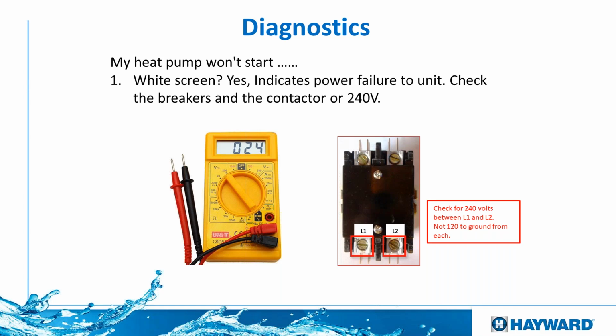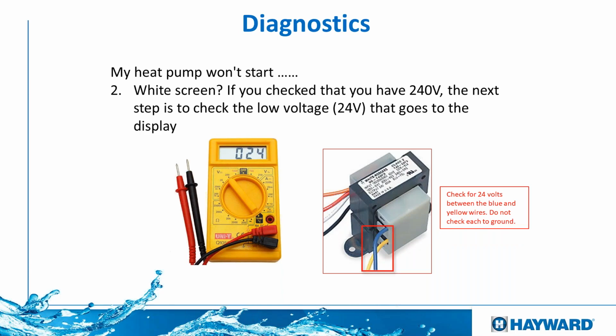So again, if the heat pump won't start, the screen is white, what do we have to check for? Make sure we have 240 volts coming into the contactor. If we don't, then we have to go and see the breaker. Make sure the breaker is on, make sure the breaker is okay, make sure the cables are okay. If the heat pump still has a white screen, but we do have 240 coming in, then we got to make sure that the transformer's got 24 volts going out. So just double check those two wires that you see there, the blue and the yellow, and make sure you have 24 volts.